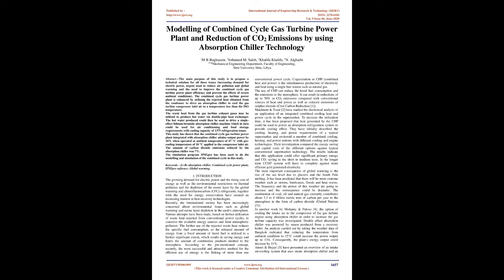1,375 refrigeration tonne. This study has shown that the combined cycle gas turbine power plant integrated with absorption chiller increases output power by 10% when operated at ambient temperature of 47 degrees Celsius with pre-cooling temperature of 10 degrees Celsius applied to the compressor inlet air. The amount of carbon dioxide emissions reduced by the absorption chiller was 7%. The simulation program IPSEPRO has been used to do the modeling and simulation of the combined cycle in this study. Keywords: LiBr absorption chiller, combined cycle power plant, IPSEPRO software, global warming.